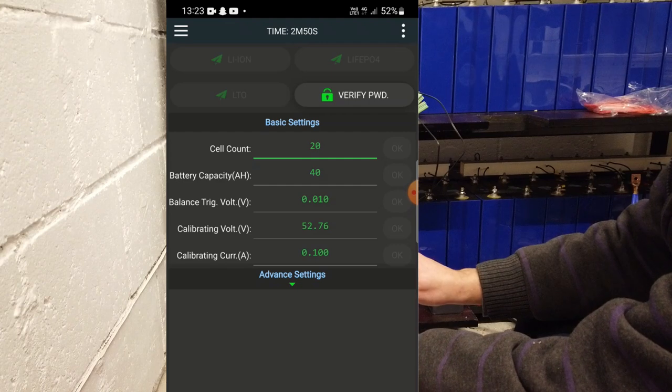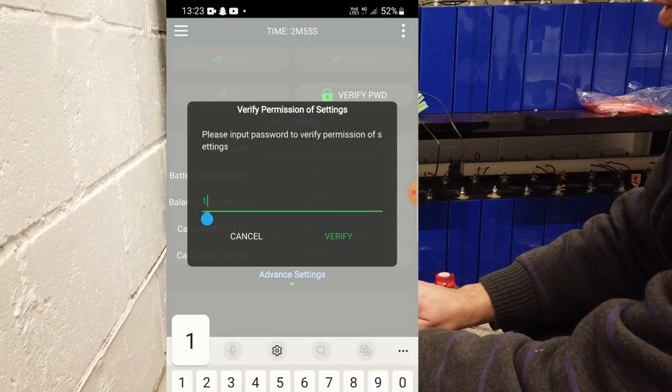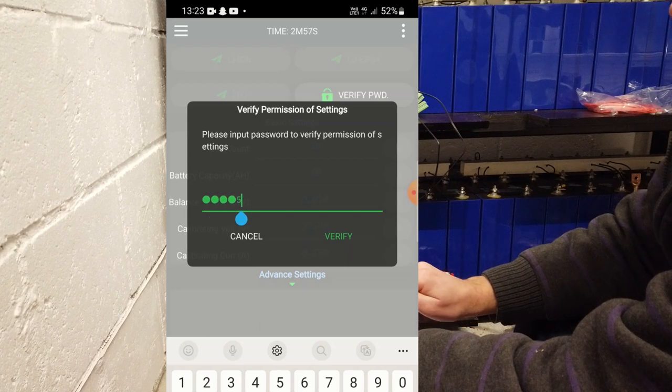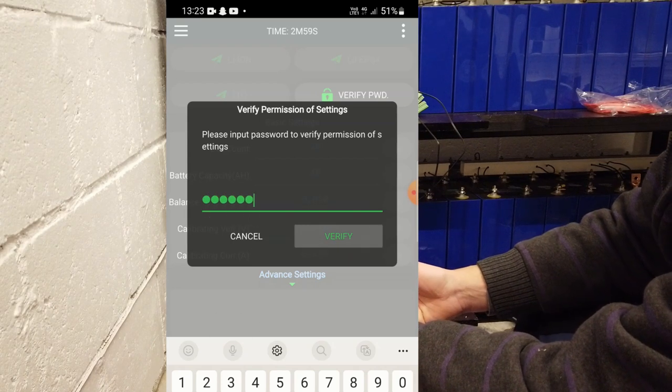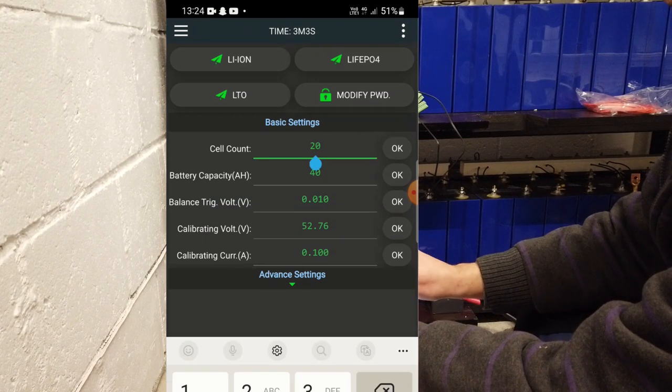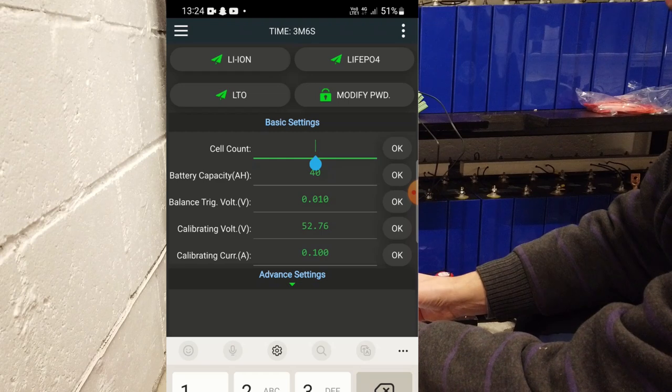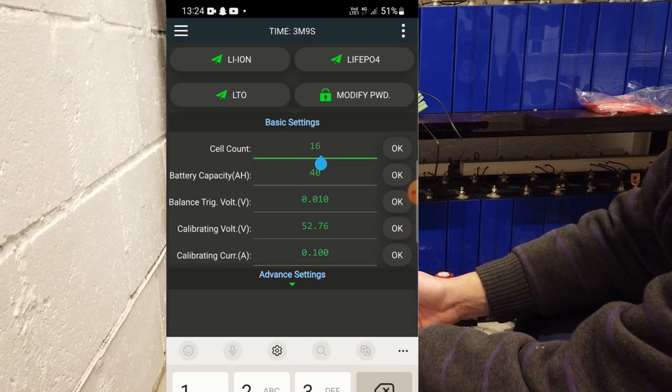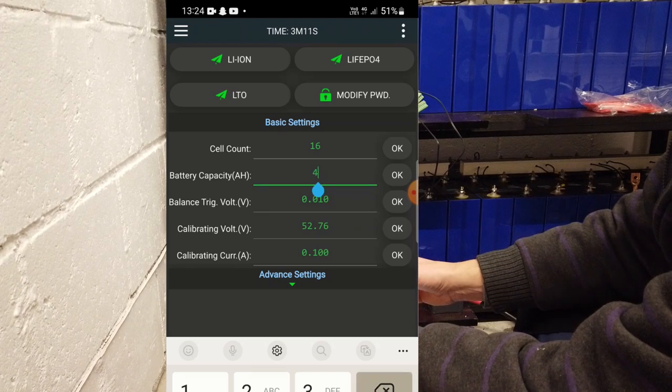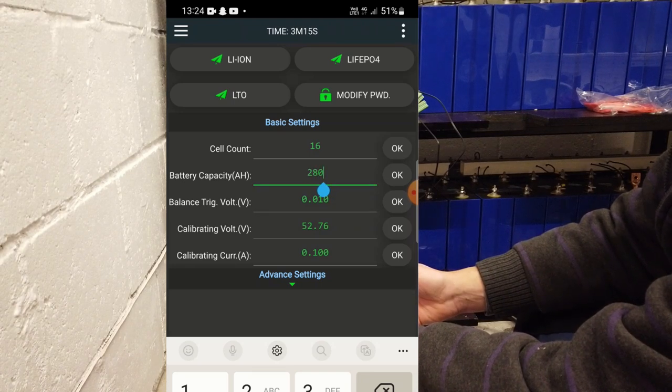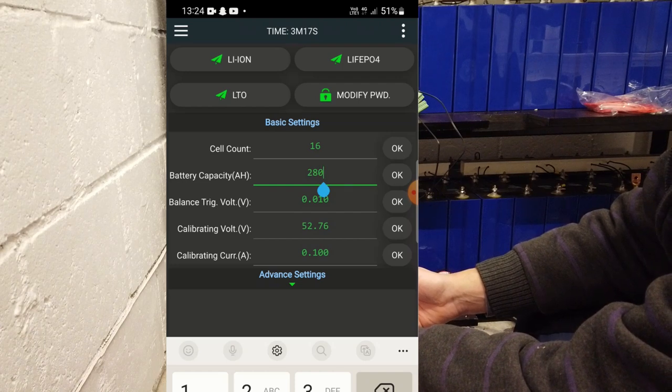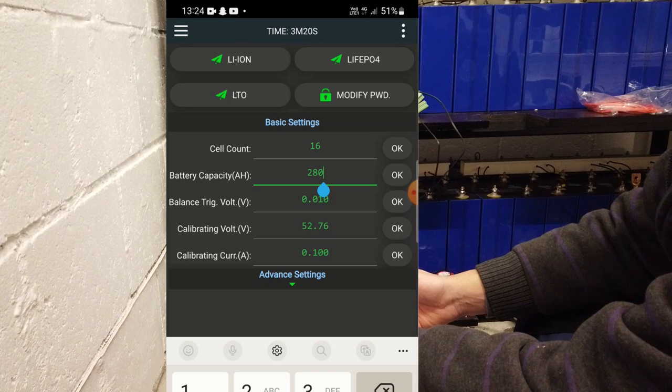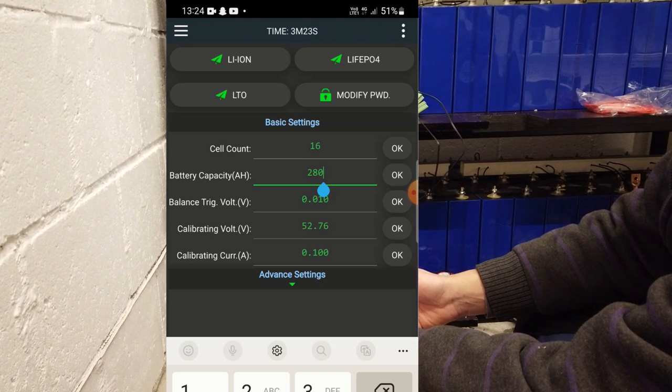Okay, we have to verify passwords. This is 1234. You should change the password afterwards, of course. We have 16 cells. Capacity, 280 amp-hours. Balance trigger voltage, 0.01. Okay.